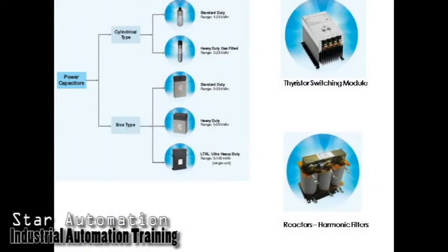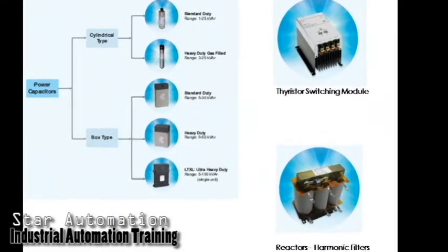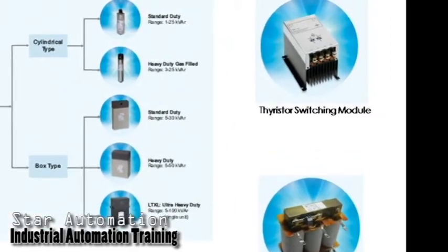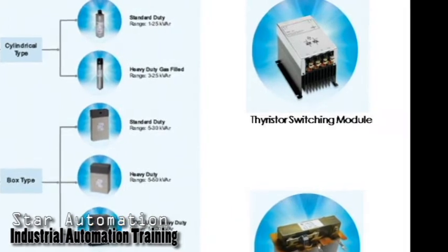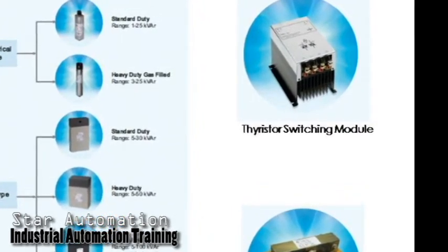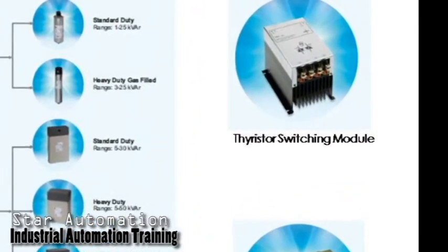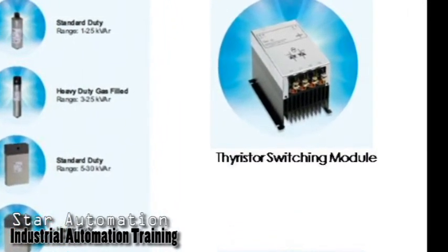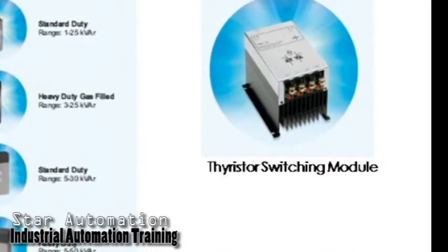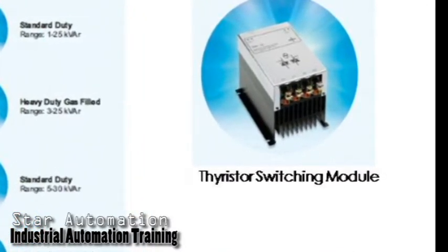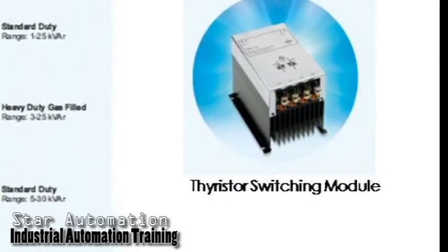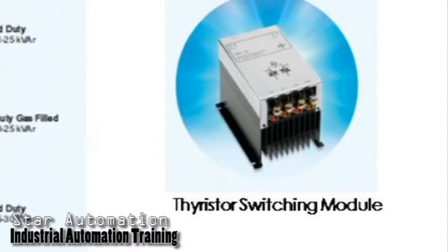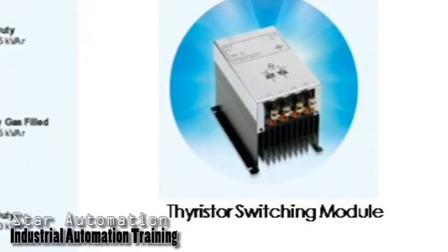Thyristor switching module is an electronic switch for dynamic power factor correction. The thyristor switch offers fast, electronically controlled, self-observing operation, capable of switching PFC capacitors within a few milliseconds, nearly without limitation to the number of switchings during the capacitor lifetime. These switching modules are easy to install, have a fast reaction time of 5 ms and come with built-in indications of operations, faults and activation. These thyristor modules are very compact and operate at lower power losses.